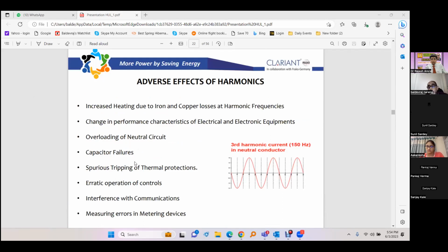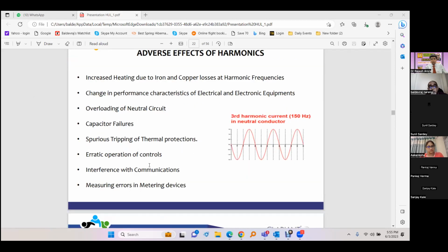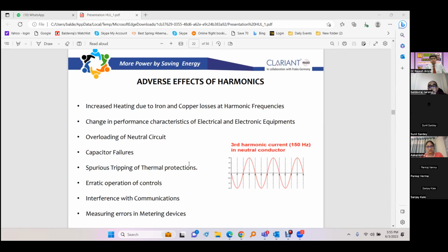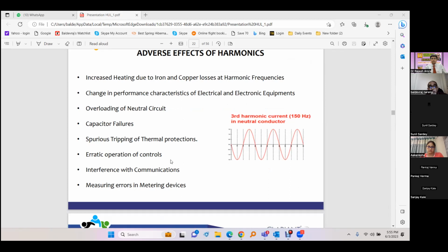Their impedance to harmonic currents, to higher frequency currents, is very low, and all the harmonic currents find their way through the capacitors and the capacitor fails. Whenever we find excess failure of capacitors, that means the harmonics are there. Then there are spurious trippings of thermal protections. The bimetal overload relays or the thermal releases maloperate because they are getting operated due to harmonic current. The fundamental current could be normal, still they operate. Then the controls also have erratic operation because they are also not designed for harmonic currents.